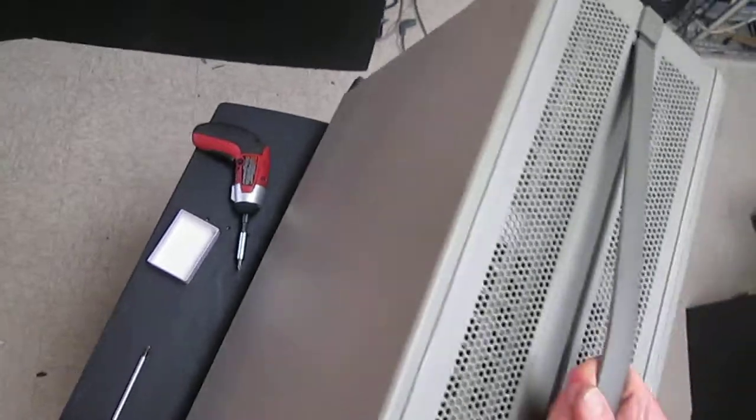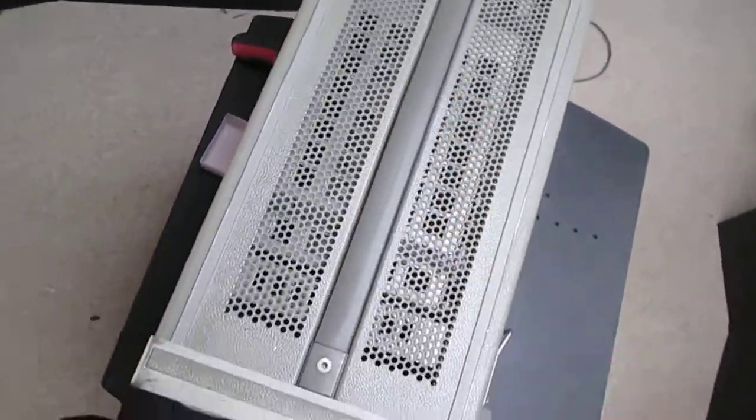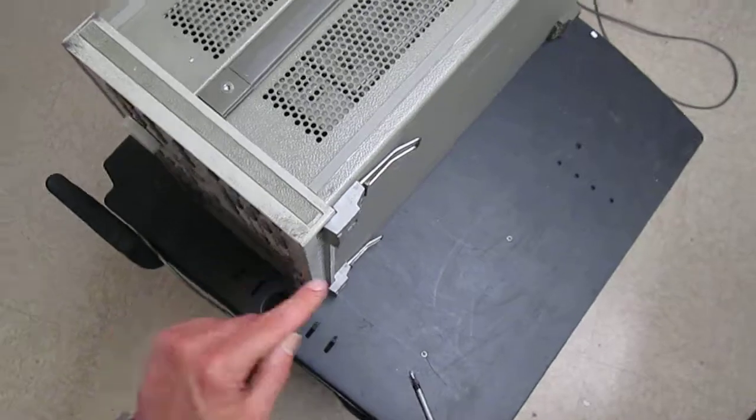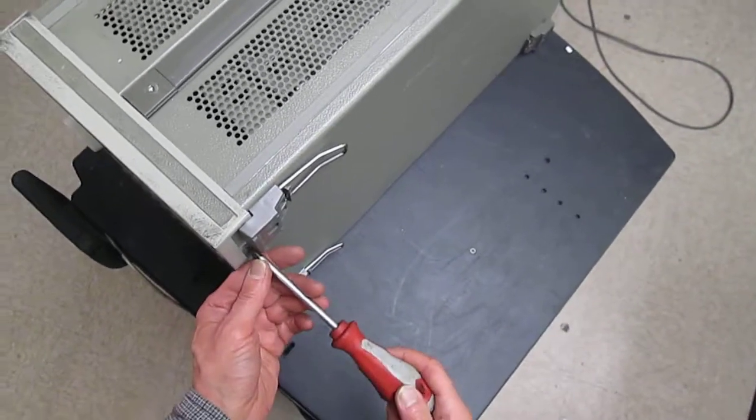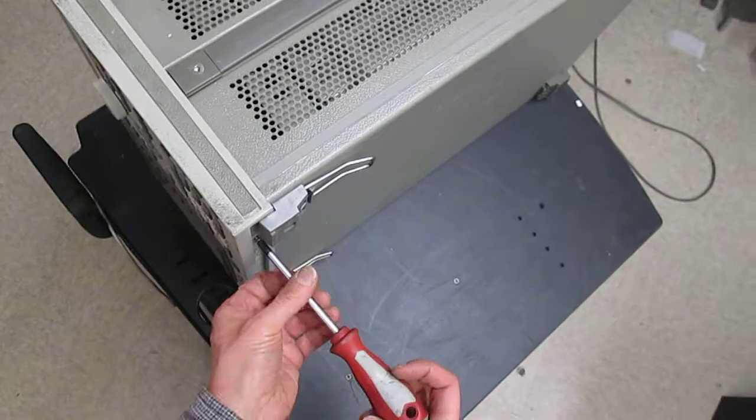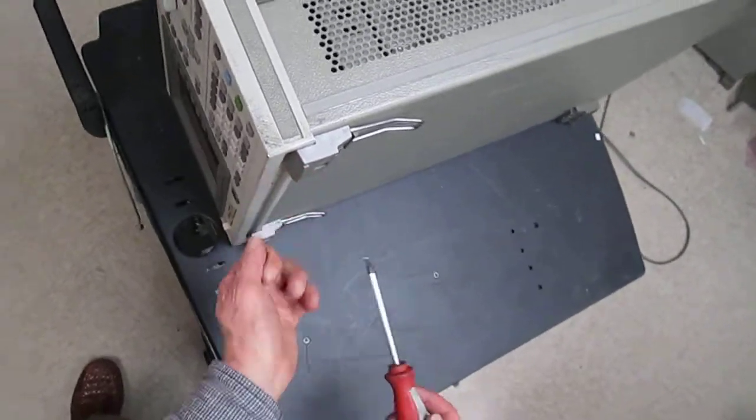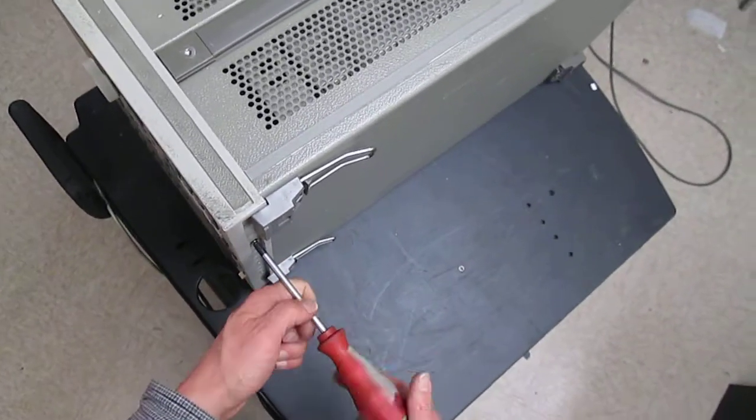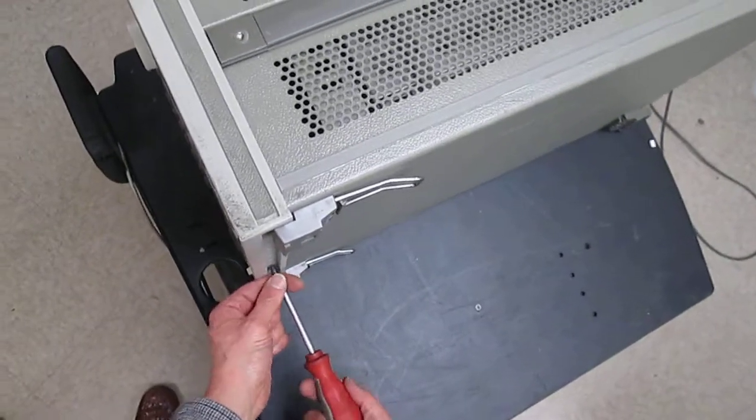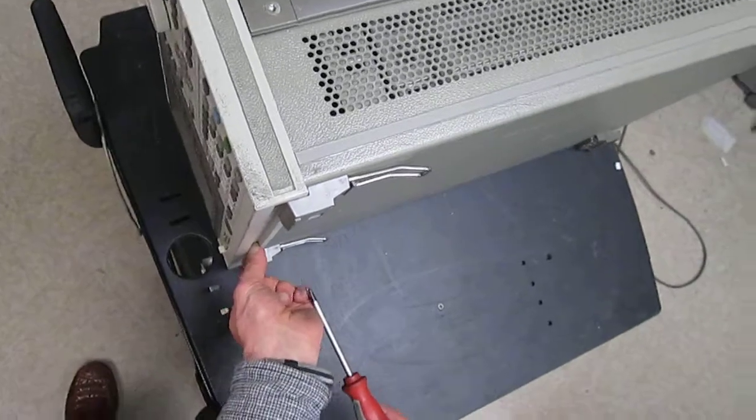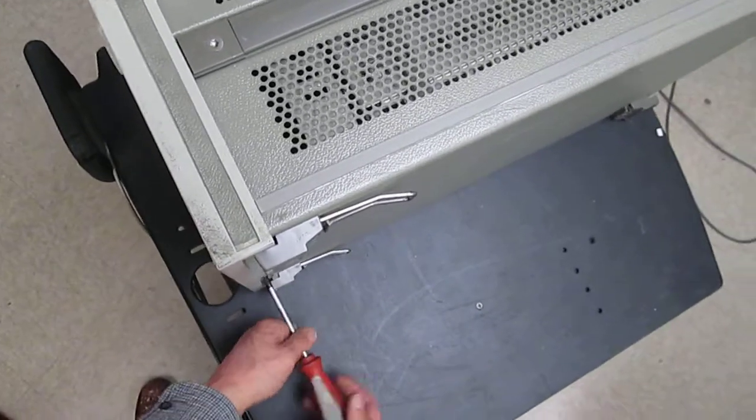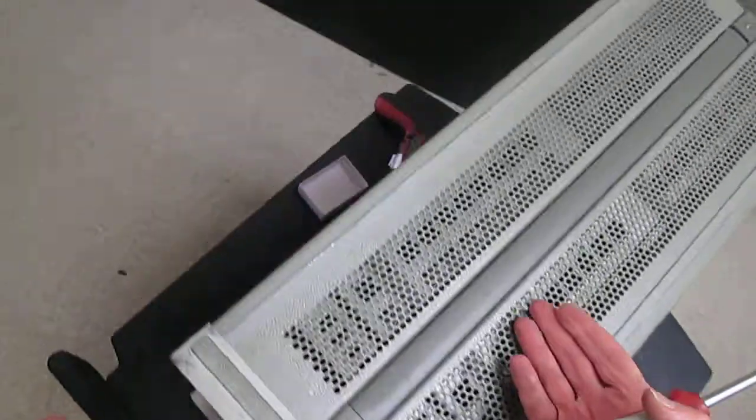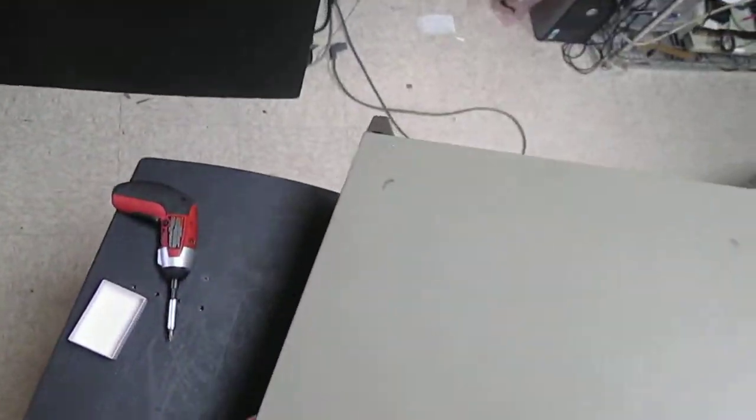Let's begin by removing the screws from the bottom of the analyzer. These screws hold the front panel in place. There are four screws on the bottom, and we remove all four. Let's set the analyzer back on its bottom feet.